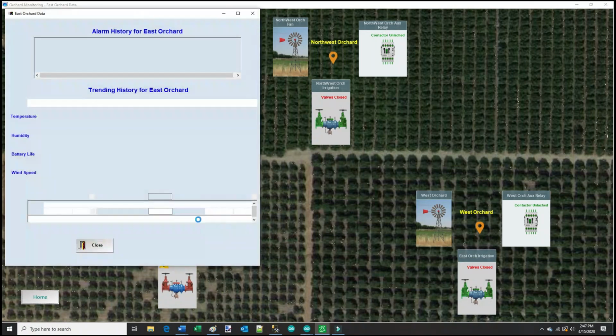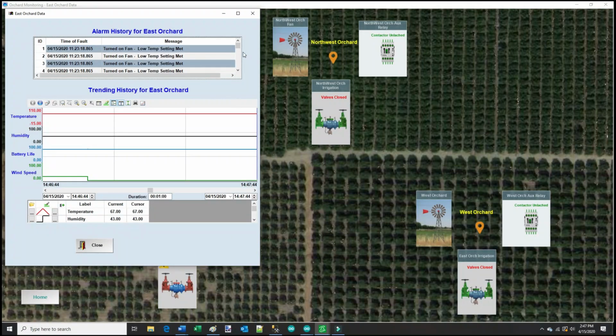And if I come in here, these are alarm history and trending, and you can see at 2:33 the alarm came on for both the fan and the irrigation. And this is off my SQL database, and you can see I'm trending here. See the wind speed has changed. So I'm trending temperature, humidity, battery, and wind speed. And currently it's 67 temperature. Wind speed is 8 miles an hour.